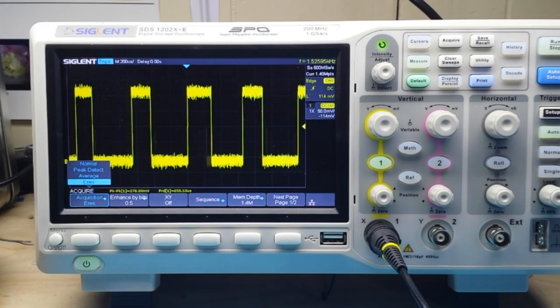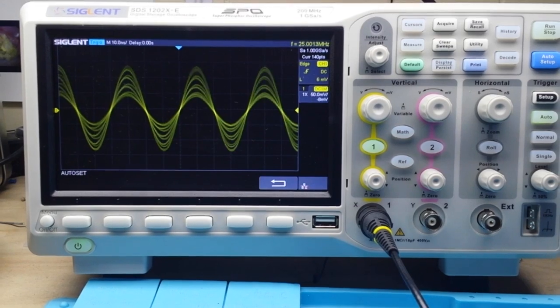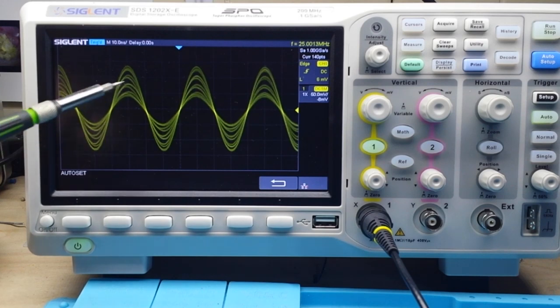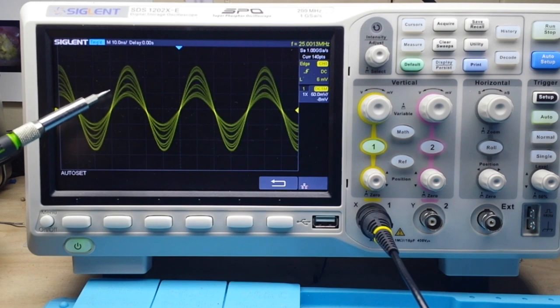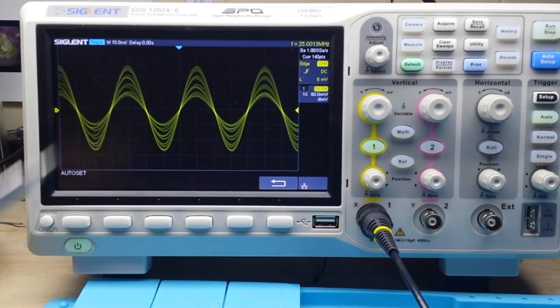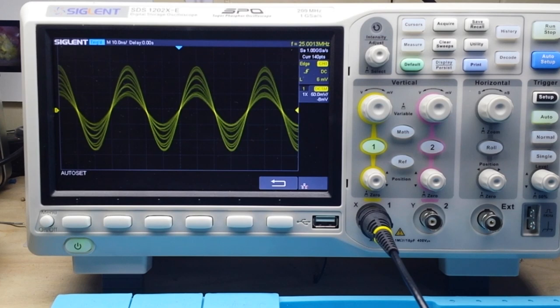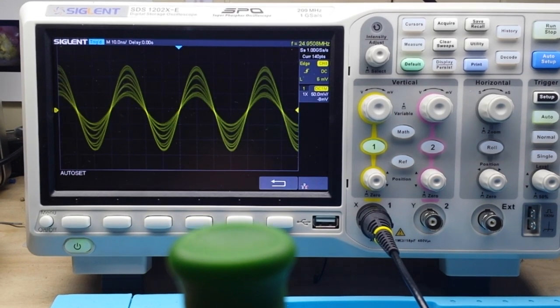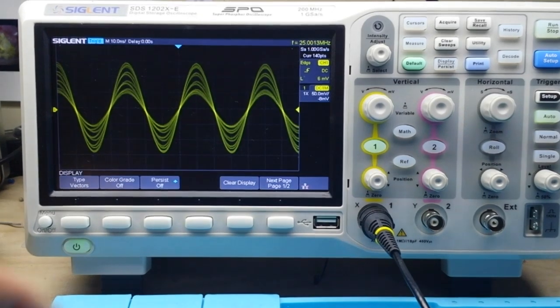The signal we're looking at here is an AM signal — amplitude modulation — meaning that while the frequency of the signal remains the same, the amplitude changes. That's the modulation. We have a carrier wave, and on top of the carrier wave is the modulation which contains information — it could be voice, data, or continuous wave. One of the really neat features of this scope I want to show you is called persistence.